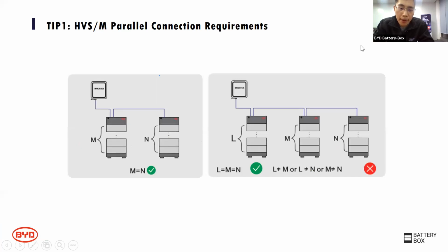For parallel systems, please make sure when you parallel the high voltage systems that every single tower has the same module number, because the logic for high voltage is that each module connects in series to get a high voltage, and for multiple tower parallel connections, each tower has to be the same voltage. Otherwise, the whole system doesn't work.